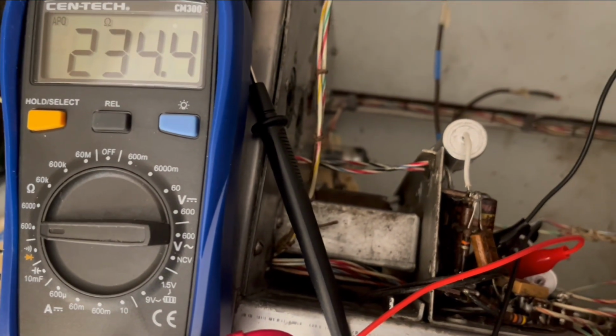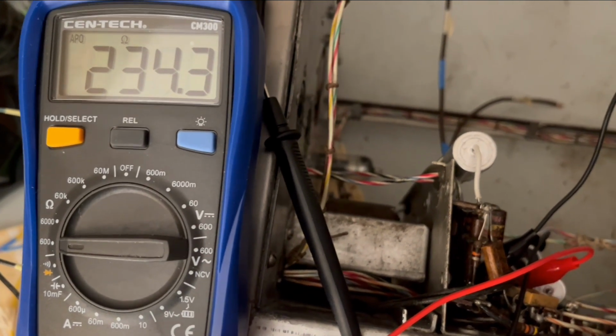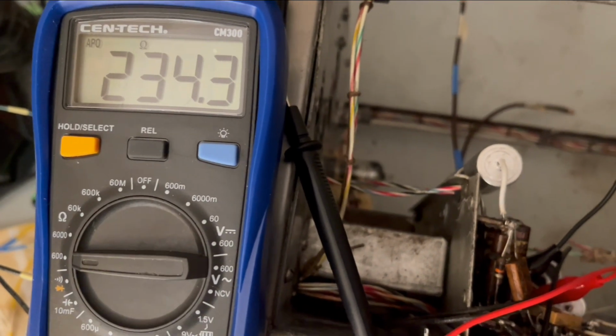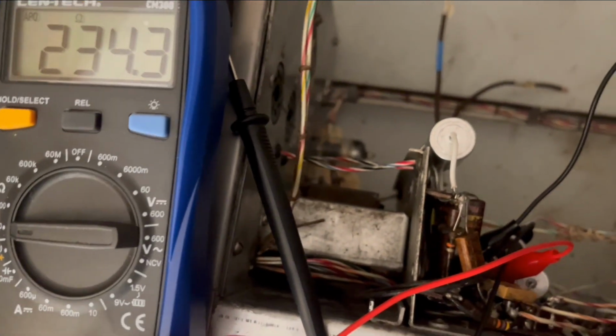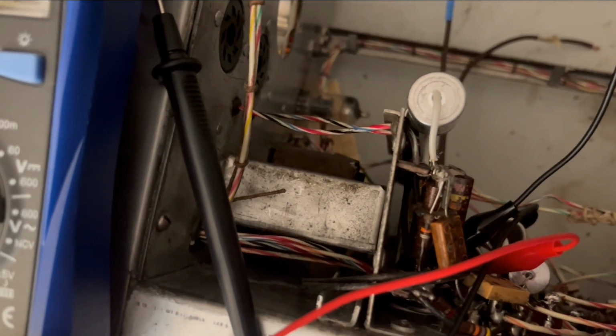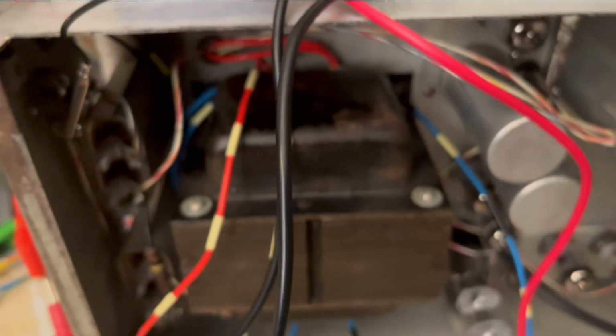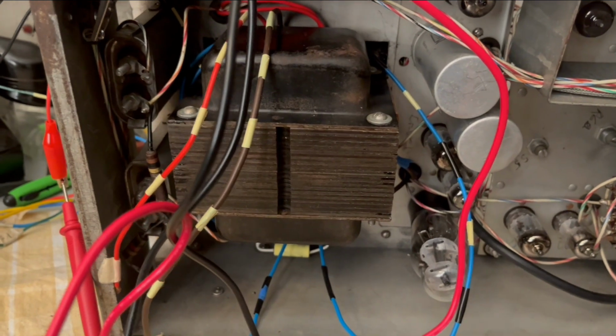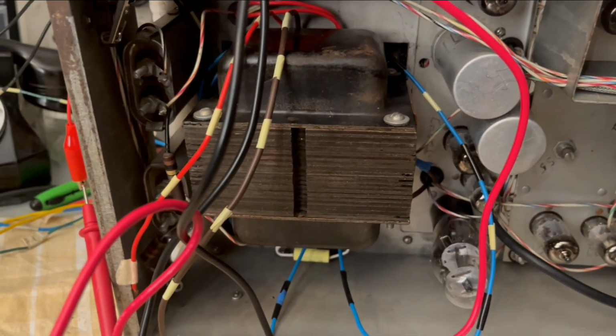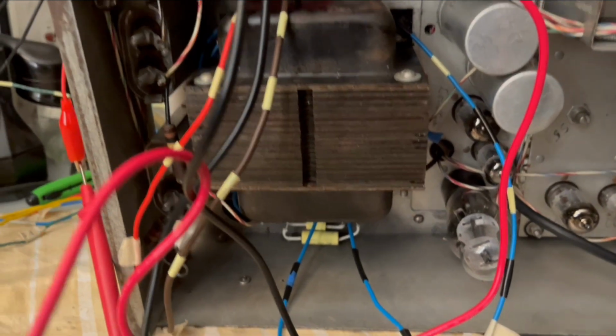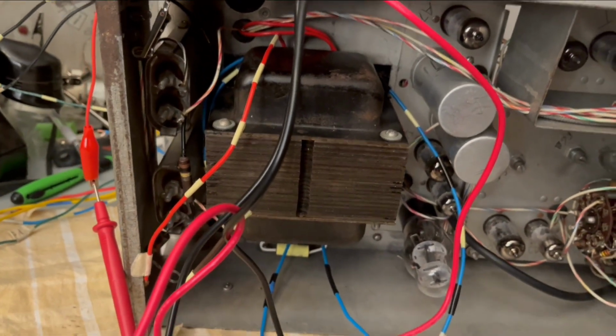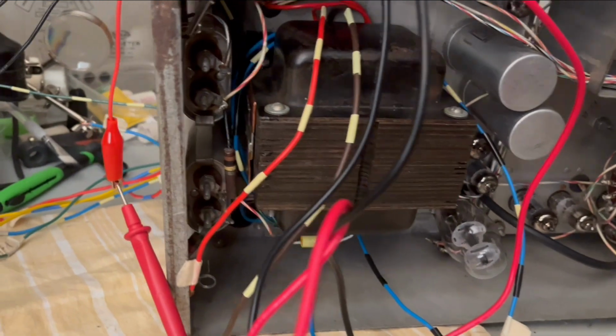I've reinstalled the choke back into position after cleaning up underneath it a little bit to make sure there was nothing else down there. Like I say, I didn't really need to unmount it, because I'm taking an ohm reading on it right now and getting 234 ohms, so it's definitely not shorted. At the same time, I've mounted the transformer back into place, and I've color-coded the wires so I know which is on which end of the transformer.